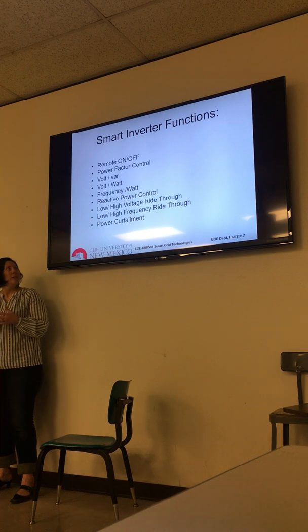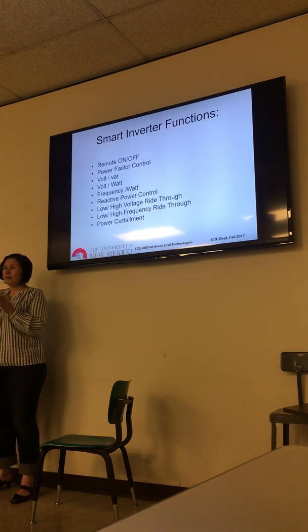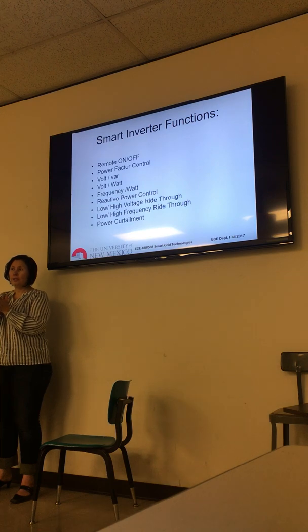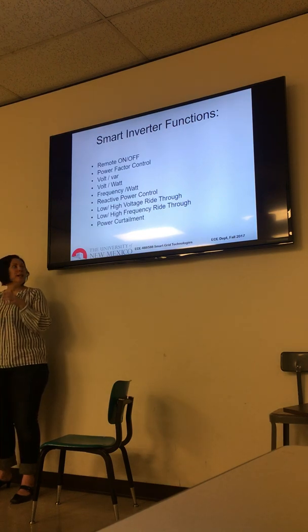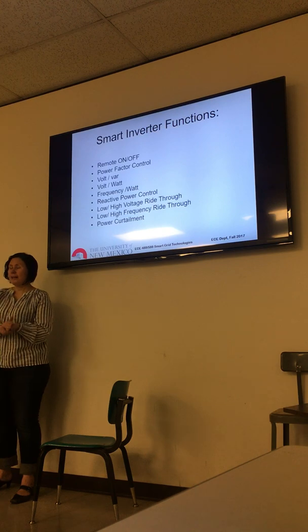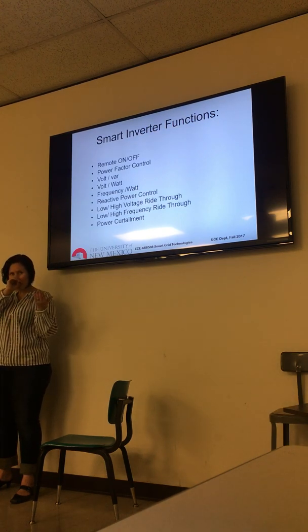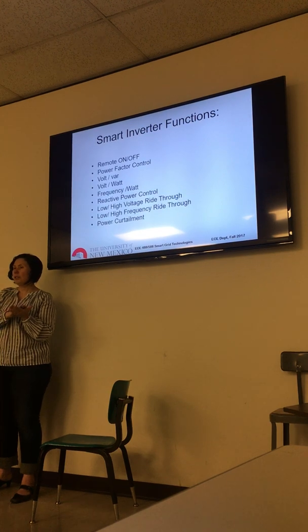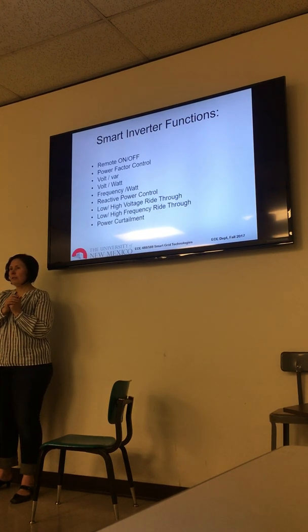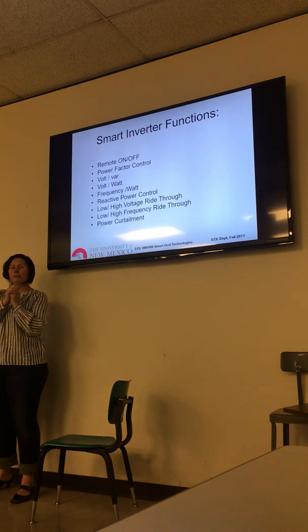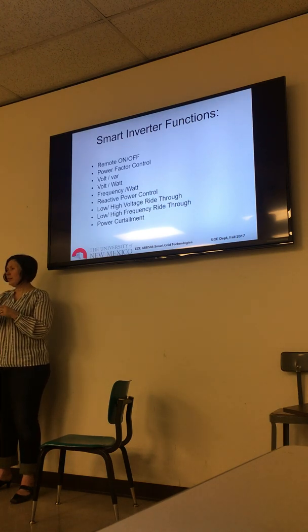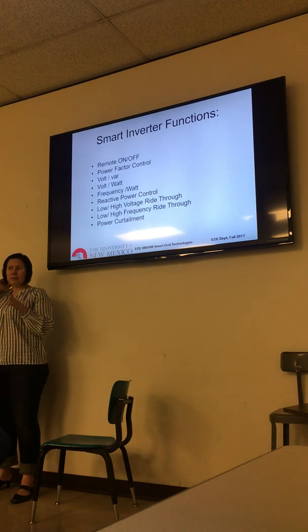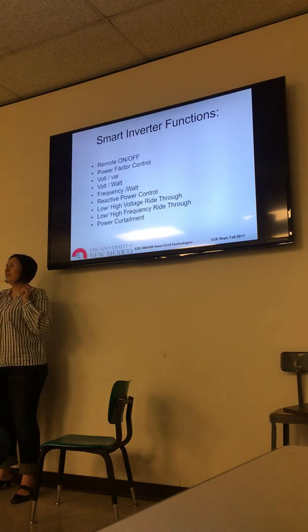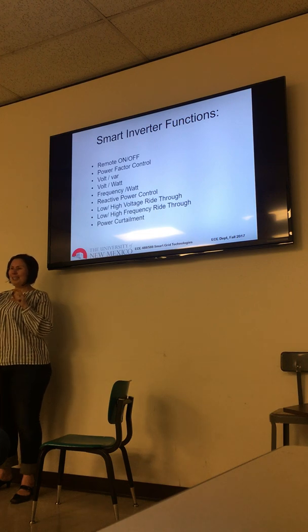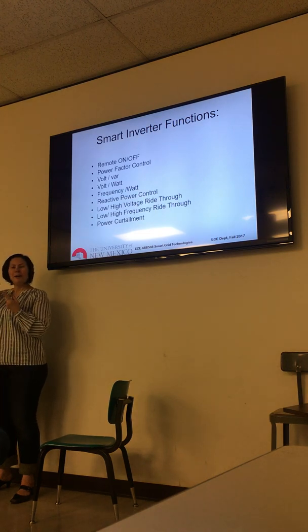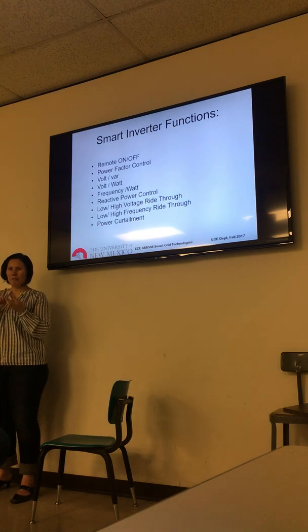But power factor control, that's where, oh, you guys don't see my mouse. So power factor in an inverter is normally designed to take DC power and convert it with the highest efficiency to AC. And so normally that highest efficiency would mean a power factor of what value? 1. So until pretty much now, an inverter had one job in life, to take DC and convert the DC to AC power in the ANSI range at power factor 1.